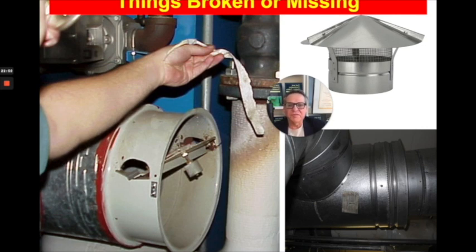To my left, what you're seeing is called a barometric relief damper — a device installed if you have too tall of a stack or too much suction in a system. The little damper is supposed to only allow air to go in and not allow things to come out. You can see by the discoloration on the pipe insulation that there have been flue gases coming out of here for some period of time. This is very dangerous. If we're making carbon monoxide and it's escaping through a barometric relief that's not functioning properly, we could really hurt or kill people. Make sure the damper is functioning and only allowing air to go in.